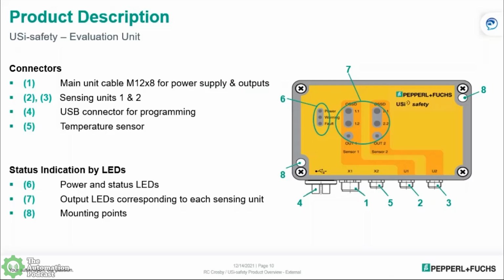And just to clarify, the evaluation unit is not a safety controller. It's not a safety relay. It does output OSSDs, so it does require you to hook that up to a safe PLC, which can handle OSSD outputs, or a safety relay that can handle OSSD outputs to complete the safety function, to complete the monitoring of the safety function. All right, so that's an important takeaway. This unit will need either a safety relay or safety PLC to go with it because it's outputting the OSSD outputs.